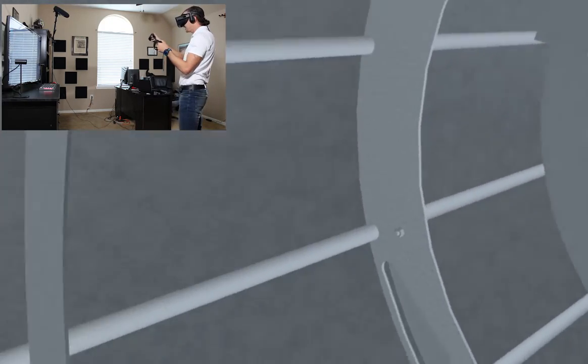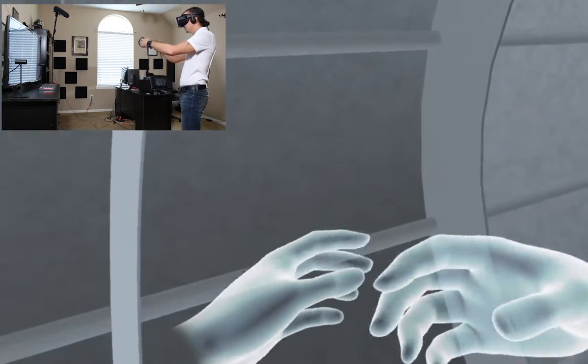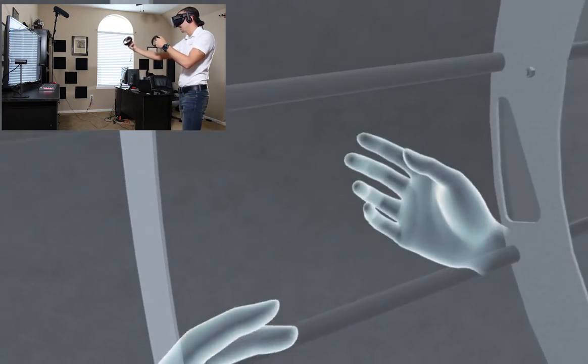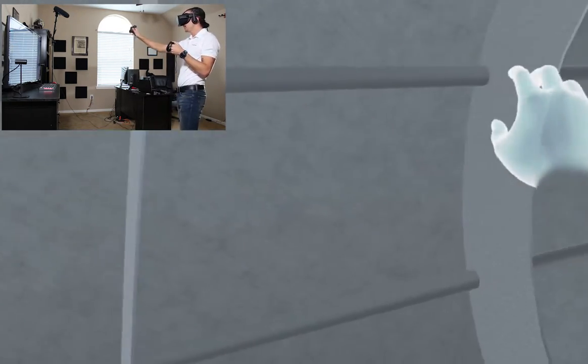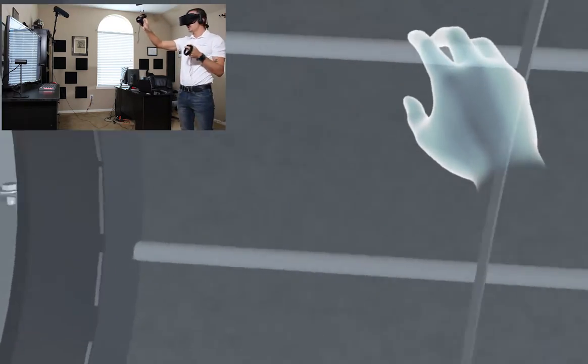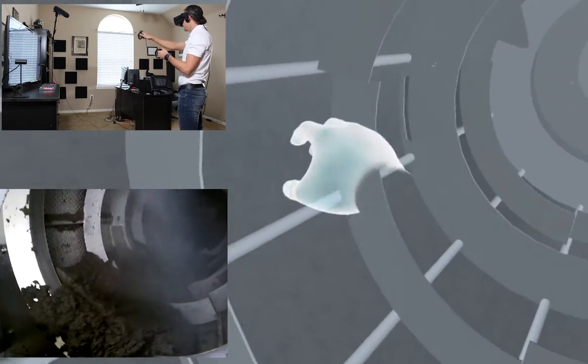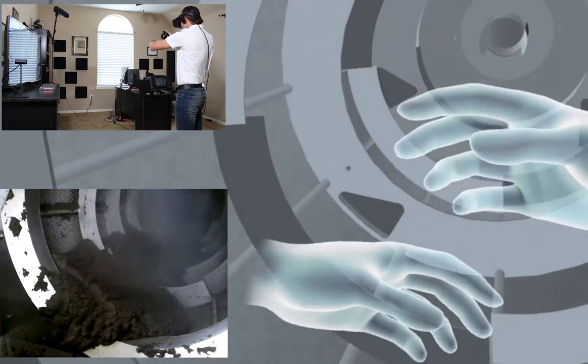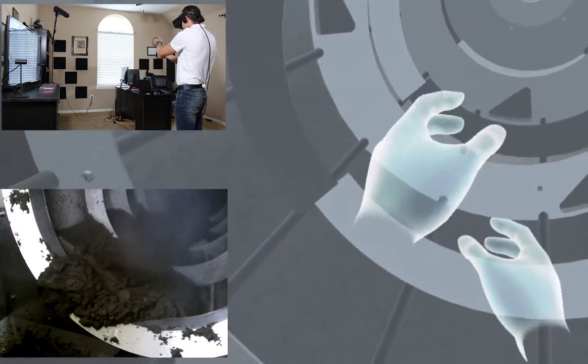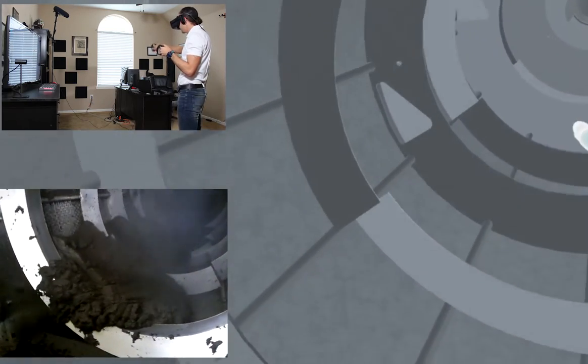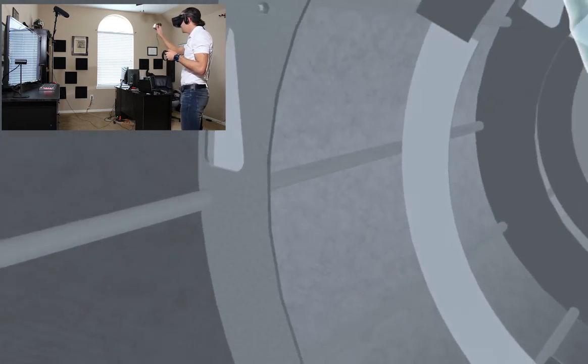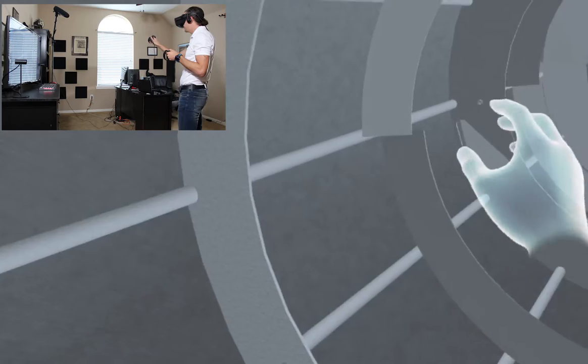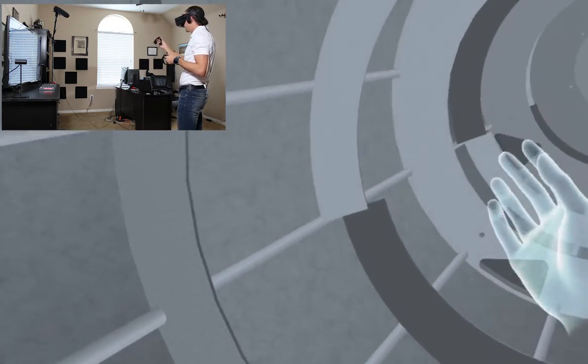Now, the second direction we want to get it to roll is this way, right? So again, we're inducing a rolling motion to continually get all that sludge and water in contact with our screening material. And to do that, we have these items here called roll bars. And these go along the entire length of the drum. And these roll bars induce that rolling motion of the sludge as it goes this way. So we're getting it to flip over and roll this direction, and we're getting it to flip and roll over this direction. And that is, again, ensuring that all that sludge and water, including the additional residence time, is also ensuring that it gets in contact with the screening material. And that's where the water release happens. And that's another huge efficiency and a huge difference you'll see of this RDT versus others on the market.